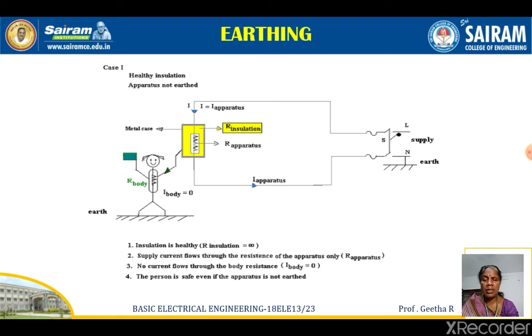Here, case 1 is shown with the condition of healthy insulation, that is, good insulation, and the apparatus shown here is not earthed. The apparatus is not earthed, but the insulation is good. So if a human body touches the body of the apparatus, there will not be any damage to the human body because of the good insulation. This insulation prevents any additional or extra current from flowing through the human body.